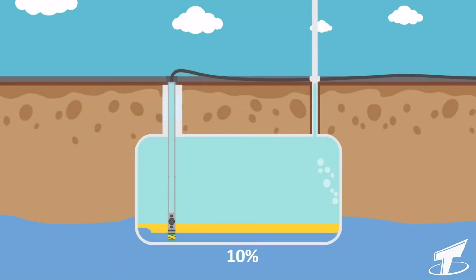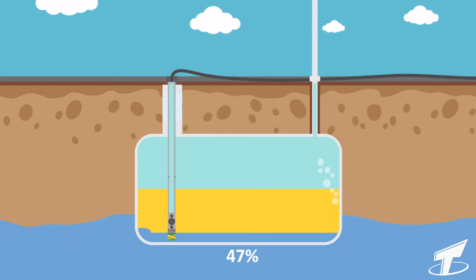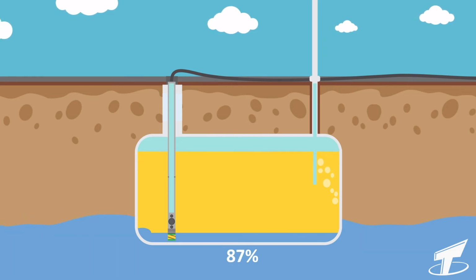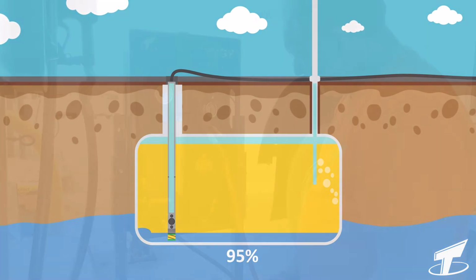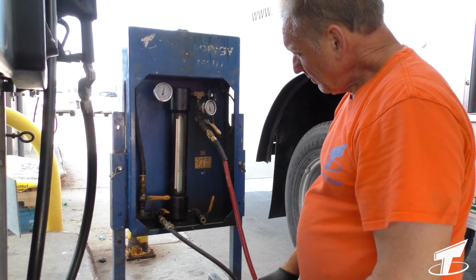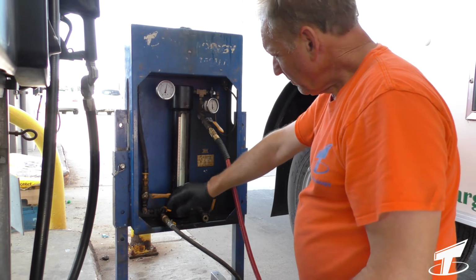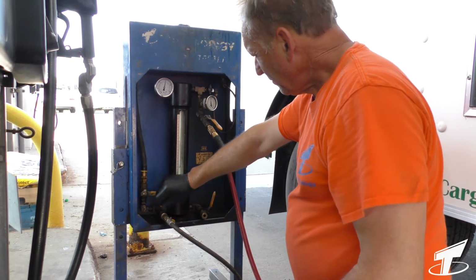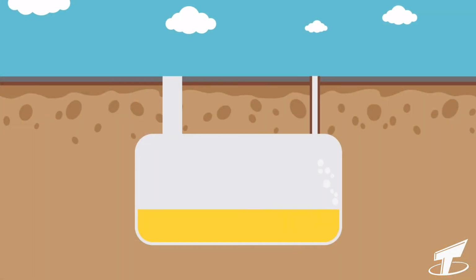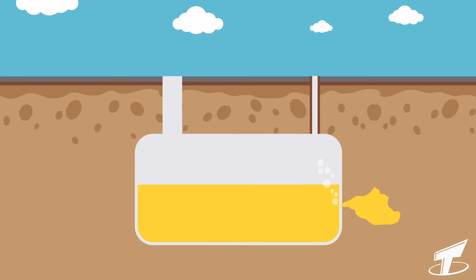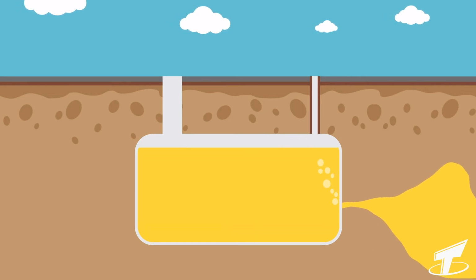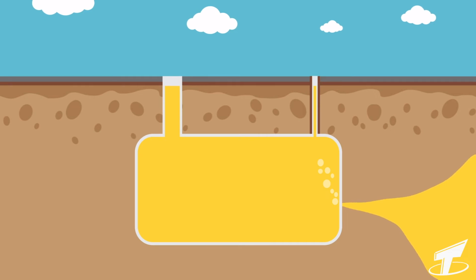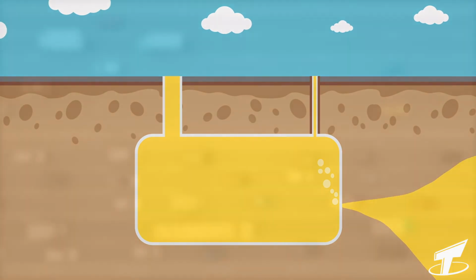Second, VacuTect is certified by third-party testing to test tanks up to 30,000 gallons with no product inside the tank. Larger tanks, up to 75,000 gallons, can be tested at levels between 60 and 95% full. Third, the test certifies the entire tank and piping system and produces a full system precision test. Fourth, VacuTect does not present the risk of creating or increasing a product release through a leakage point. For that reason, it is a more environmentally friendly technique, especially for tanks holding hazardous material.